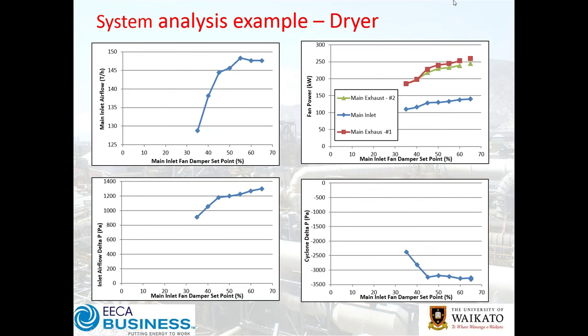To finish, let's go through a case study — a dryer. There are four charts: the upper left shows airflow in tonnes per hour based on fan damper set points. This was a fixed-speed fan with an inlet damper. The particular supply fan was operating at 65% and the exhaust fans on the system were actually at 100% — they were struggling to control the system.